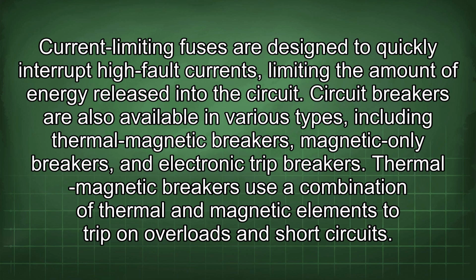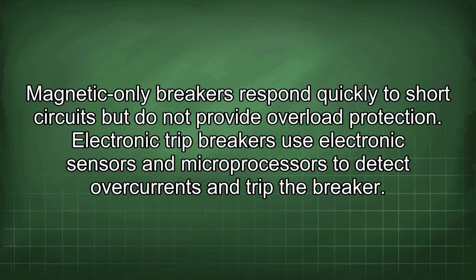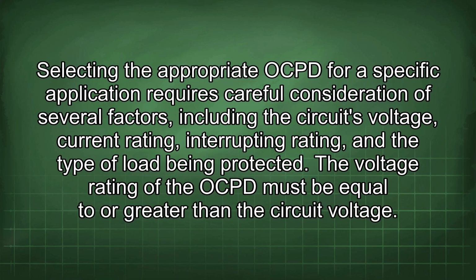Circuit breakers are also available in various types, including thermal magnetic breakers, magnetic-only breakers, and electronic trip breakers. Thermal magnetic breakers use a combination of thermal and magnetic elements to trip on overloads and short circuits. Magnetic-only breakers respond quickly to short circuits but do not provide overload protection. Electronic trip breakers use electronic sensors and microprocessors to detect overcurrent and trip the breaker. Selecting the appropriate OCPD for a specific application requires careful consideration of several factors, including the circuit's voltage, current rating, interrupting rating, and the type of load being protected.